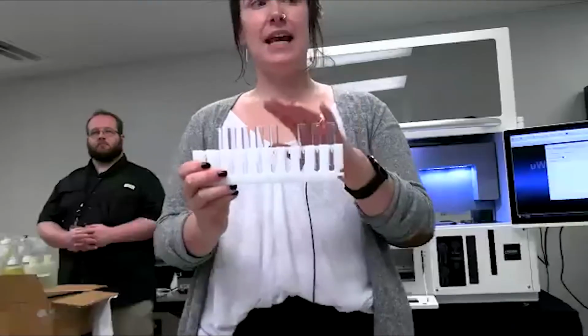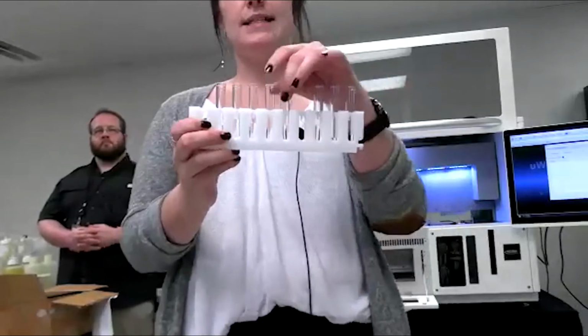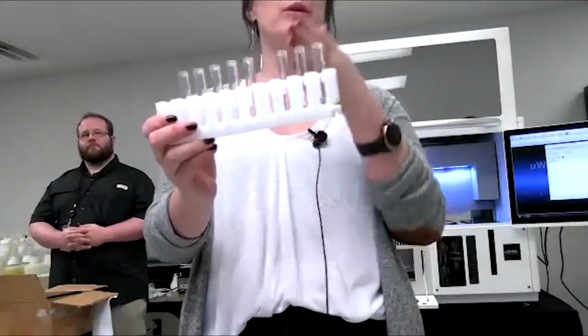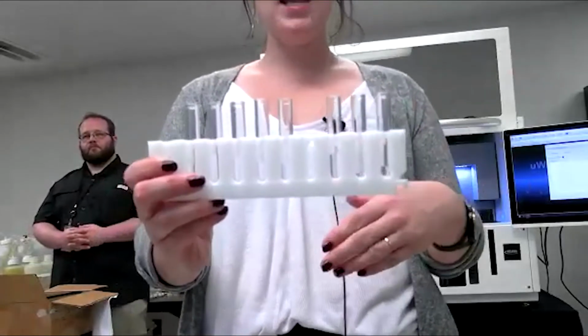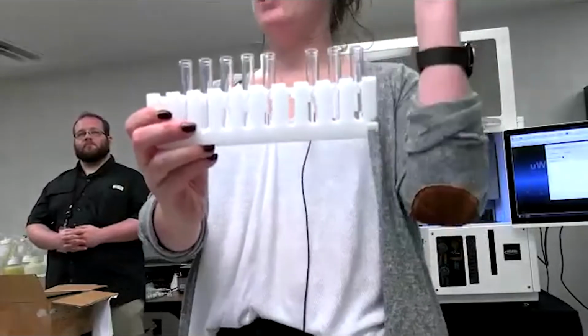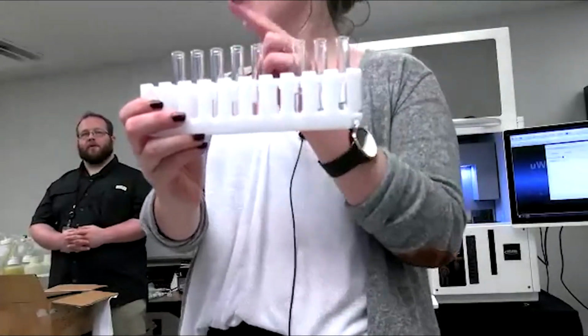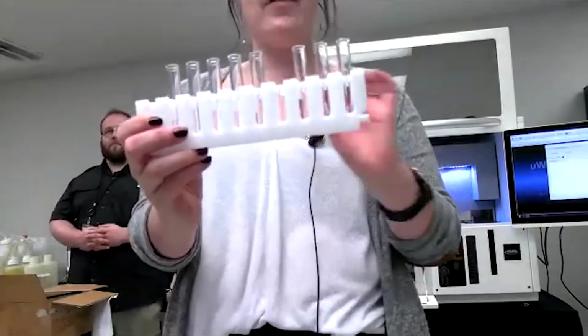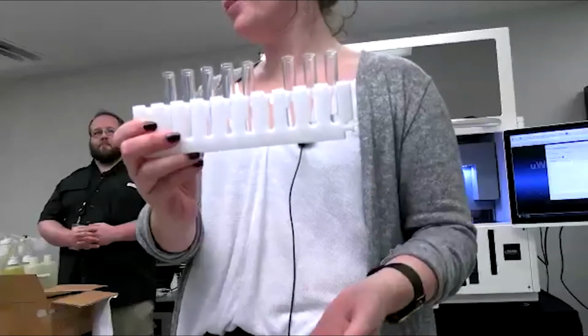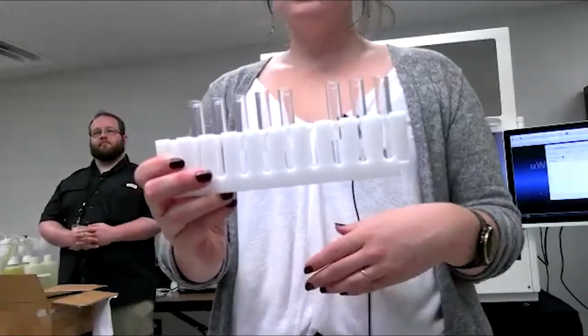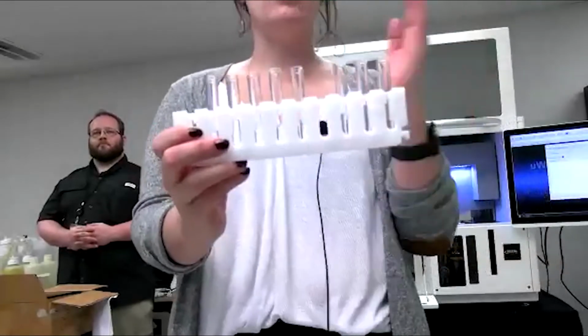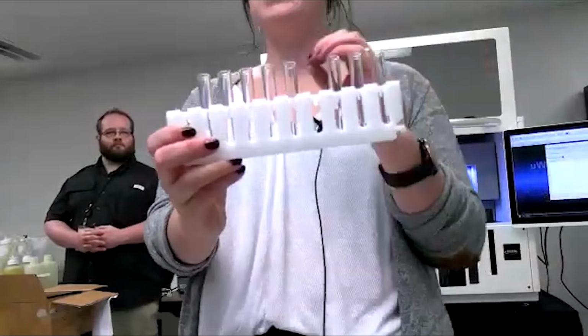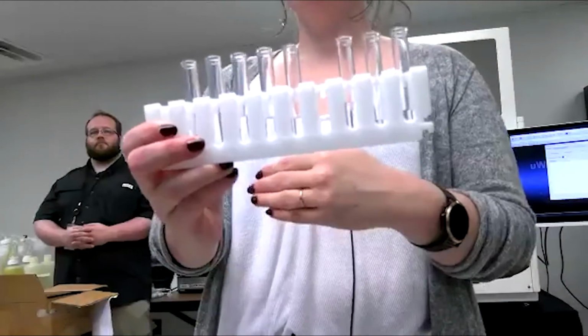If it's missing a barcode or didn't read a barcode, it'll still look and see if the tube's there and it'll still run the sample. And you can manually change that later. Yes, if it was unable to read your barcode, let's say it's in the wrong position, it will still sample from that tube and put it in the corresponding position on the sample tray. But in your work list, it will say no tube. You can actually change what it says. That's a programmable function. You can have it put in whatever message you want for when there was no barcode available, and then you can go enter in that patient data later. You can customize the error message if the customer would like to. Yes, but it won't stop your run. It won't pause anything. It'll just let you know in the run log that there were no tubes there, and then in the work list that the information ends up in, it will let you know that there was no barcode to be found.